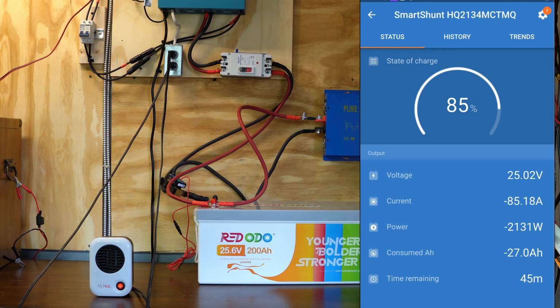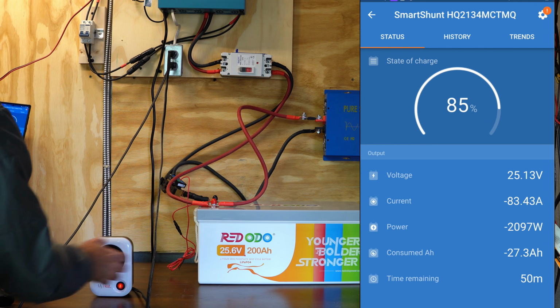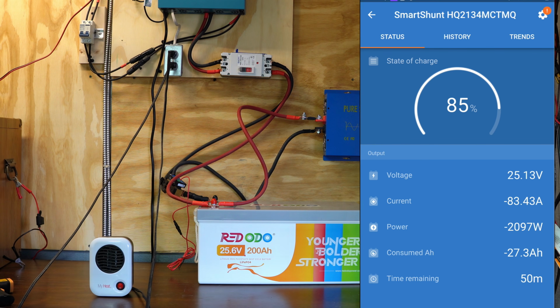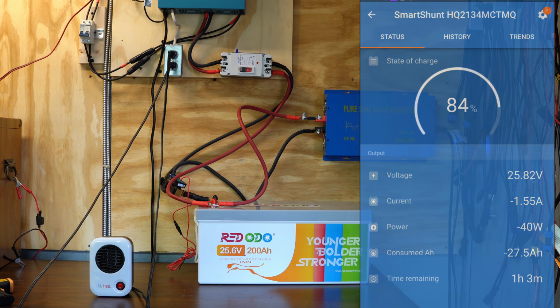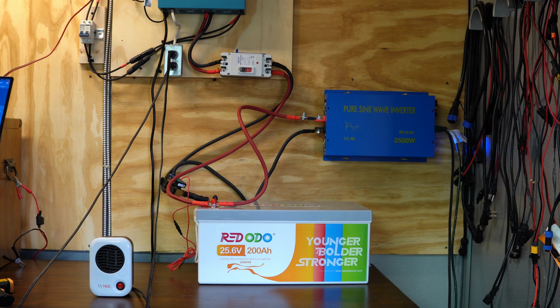Oh, there. Now we just have to follow the inverter. That was definitely the inverter, not the BMS, because the other inverter is still running and we're still pulling 2,000 watts. Let me go ahead and turn that load off. All right, pretty much turned all the loads off. All that's left is the no-load draw off the 2,500 watt inverter.